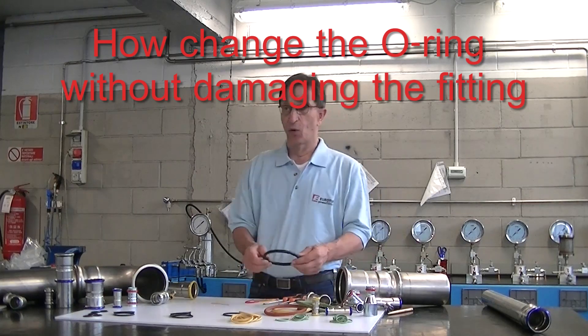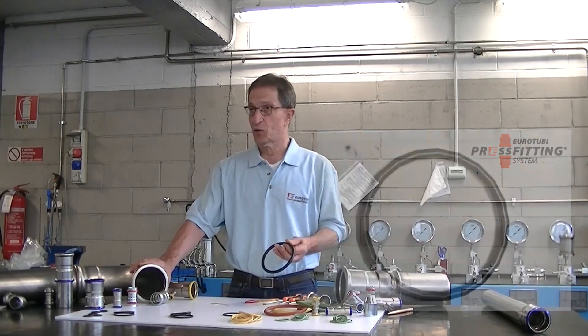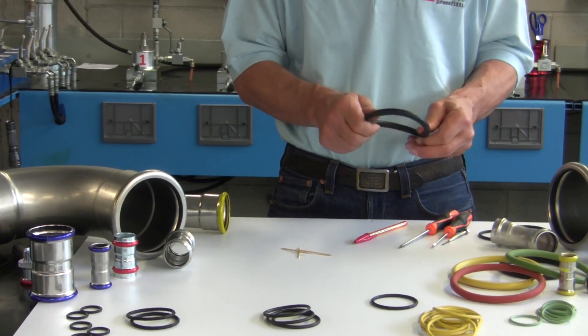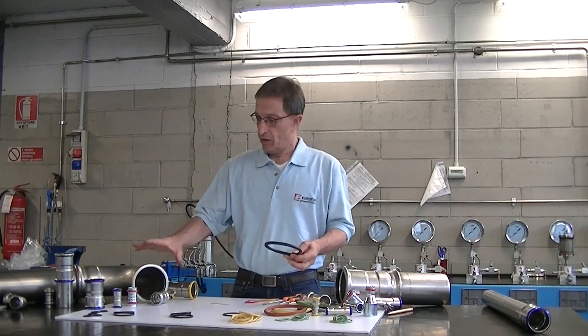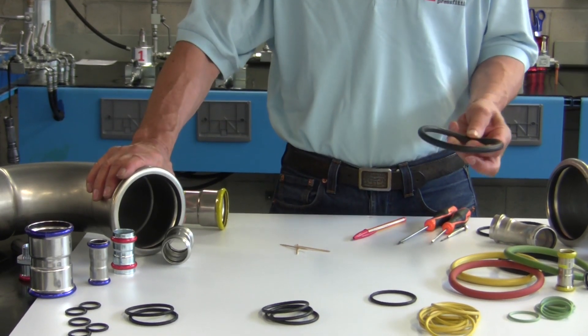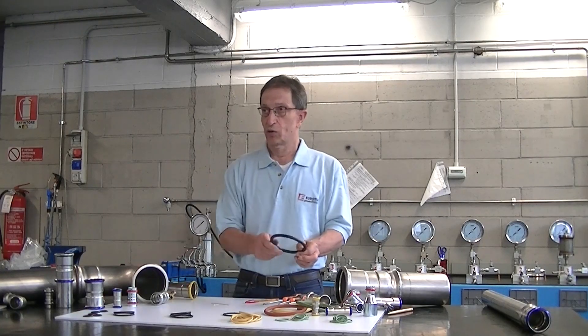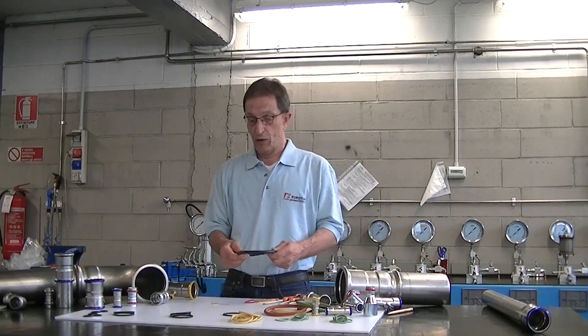Eurotubi press fittings come supplied with the EPDM o-ring. If this o-ring needs to be replaced with another type of o-ring, keep in mind that you must use o-rings provided by Eurotubi. Only these have the precise size characteristics to be used in Eurotubi press fittings. O-rings from other suppliers cannot be used for a possible o-ring change.